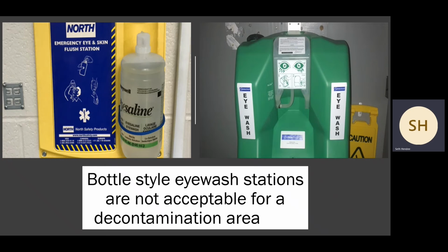One last thing to think about for eye wash stations: bottle style eye wash stations are not acceptable in the decontamination area. They have to be hands-free now. You have to be able to pull a valve, push a paddle, you name it. But it should be, you initiate the eye wash and then it just goes, and it has to be able to go for up to 15 minutes. So that squeeze bottle where you're forced to keep squeezing it yourself doesn't work. And then there are some larger tanks that are running under the same principle, except we know that they don't have enough water to run for 15 minutes.